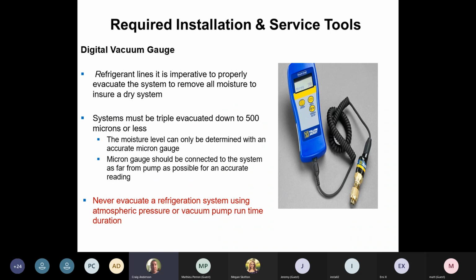Digital vacuum gauge. Make sure your vacuum gauge is working. If it's a type that needs to be calibrated or it has a date on it, get it in there and get it calibrated. If it needs a new sensor on it, order up a new sensor. This is the only way we know that we have the moisture out of the system. The R22 days are gone.